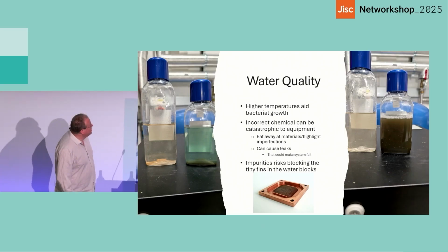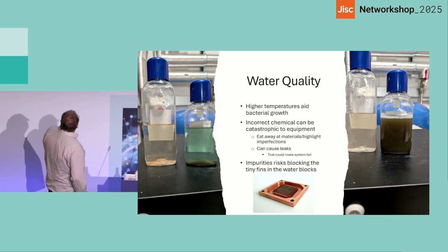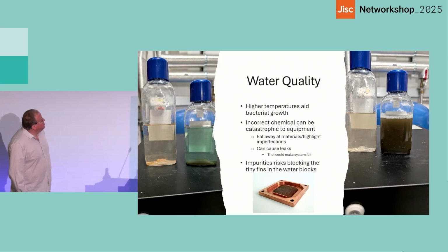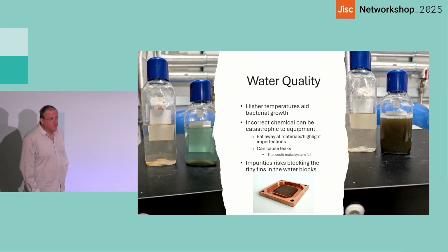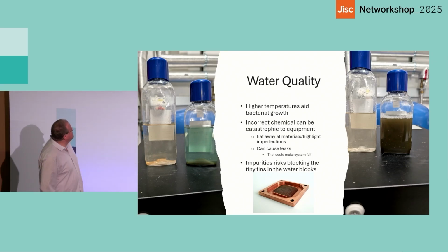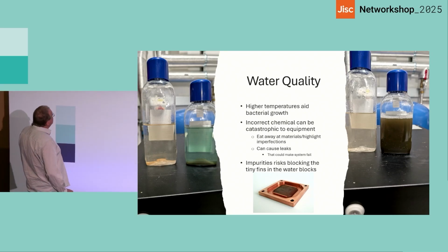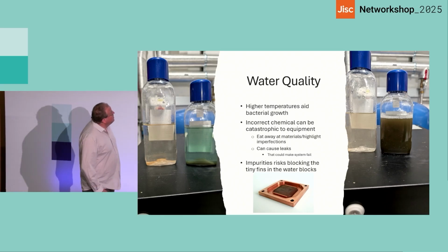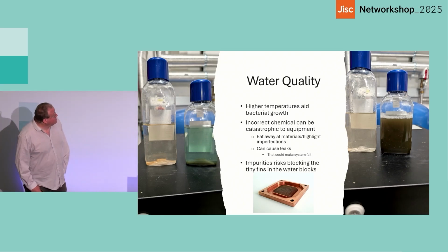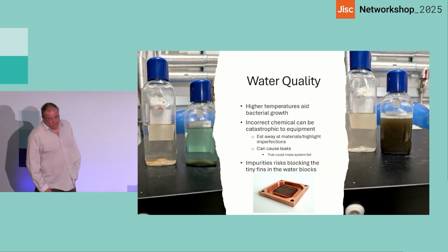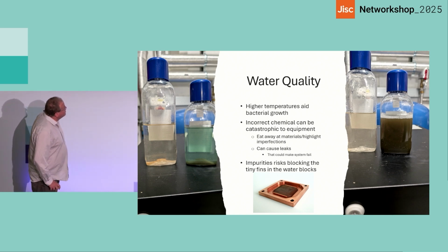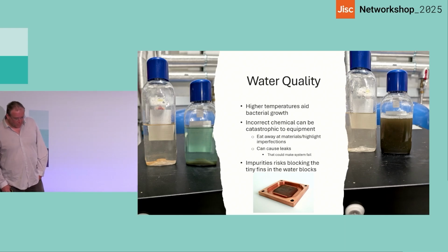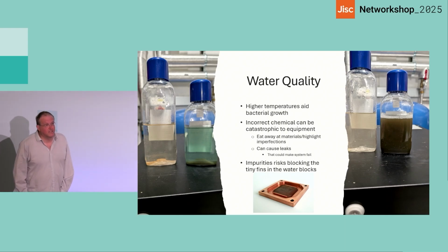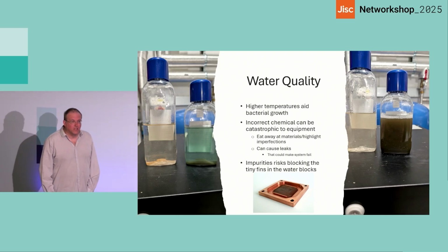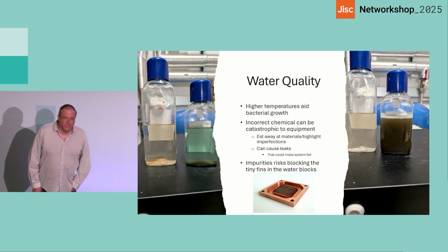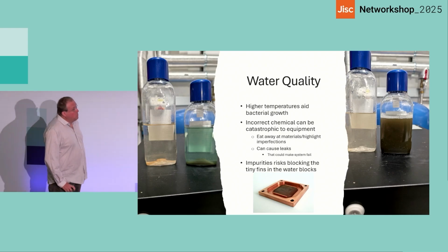If you look at these pictures, the picture on your left is a sample that's settled. When it was shaken up, it looks like the ones on the right. You can see we've actually managed to get horrible little bits in them. In some cases, it's little fine particles. In some cases, it's little bits of bacteria. So these are things that can cause problems. As you can see in the middle, I've got an example of a heat sink. This is actually not one of the HPC systems, but it was a nice one that I could show you what it looks like inside. They're tiny fins, with gaps less than a millimetre in size. It doesn't take a lot to block these. These tiny little particles, bacteria, algae growths will block it.